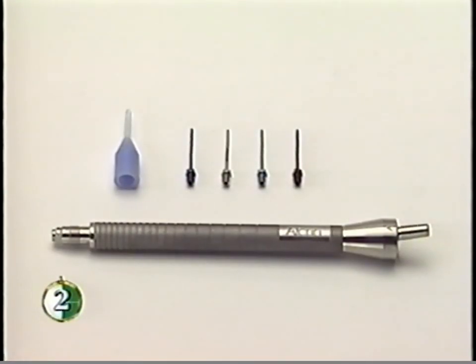These reusable IA tips, used with the threaded tip adapter, also work with the Ultraflow handpiece. They fit the threaded 8036 irrigation aspiration handpiece as well. Available sizes are 0.2 mm, 0.3 mm, 0.5 mm, and 0.7 mm. The set includes an irrigation-only adapter.